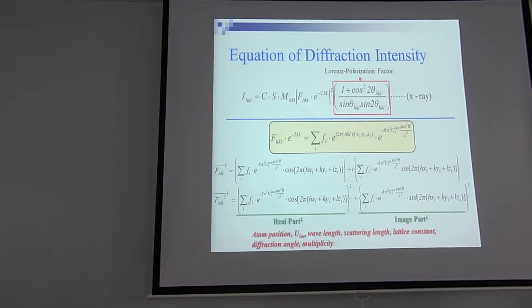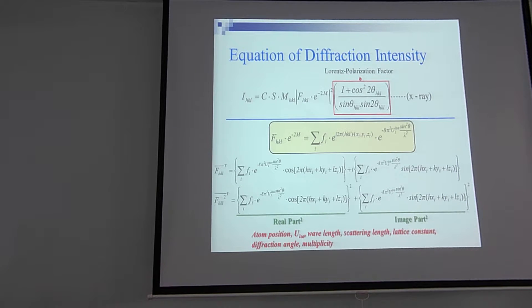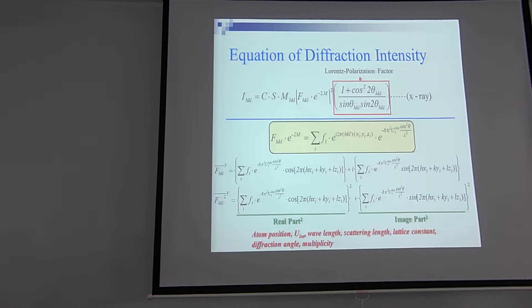I need to add one more thing — we will add one more parameter called ZERO, which means the shift of the X-ray machine. When you put in the sample it's not exactly at the center of the optical axis — it may be a little bit higher or a little bit lower — and that would cause an angle shift. So we need to add one more parameter, ZERO. That is all we need.